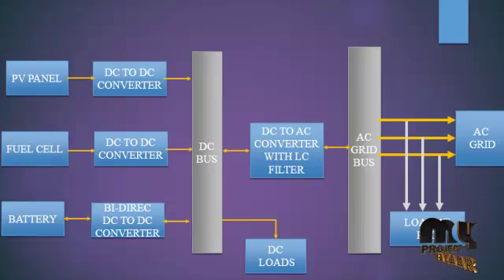Generally, from a control point of view, photovoltaic generation units can be classified into standalone and grid connected configurations. Due to the intermittent nature of PV power, battery storage is employed as a critical element in PV standalone applications to maintain the power balance in the system and enable regulation of the load voltage. Islanded microgrids share the same issue with standalone systems, since battery storage is needed to maintain the generation load balance and to regulate the microgrid voltage and frequency. In both cases, the power management strategy should consider the state of charge limits and the power rating of the battery. However, unlike in standalone PV systems, in microgrids the battery storage can be connected to the microgrid bus as a separate unit.